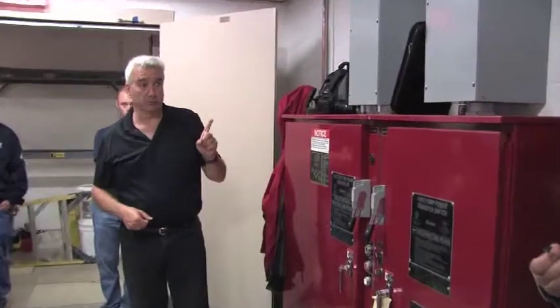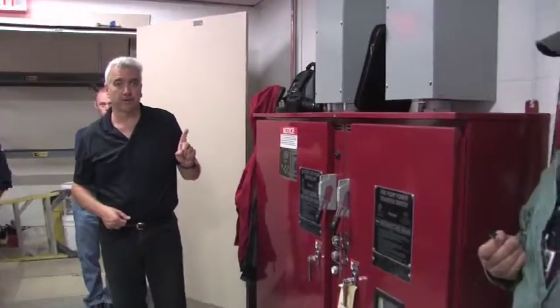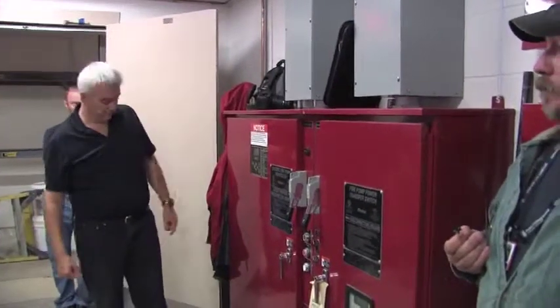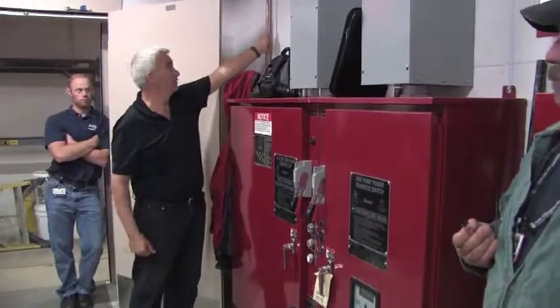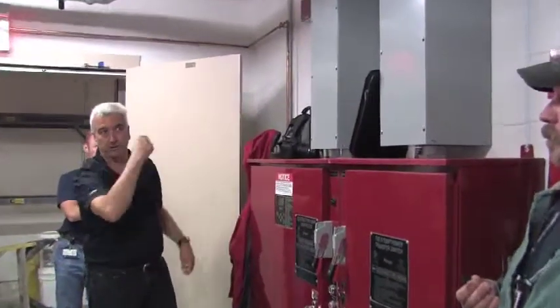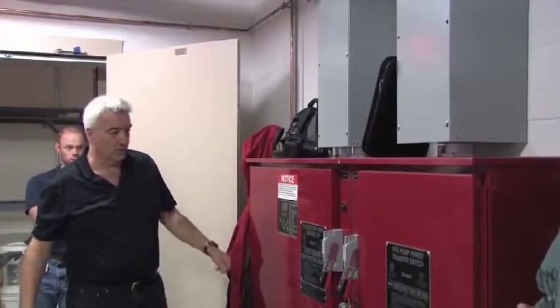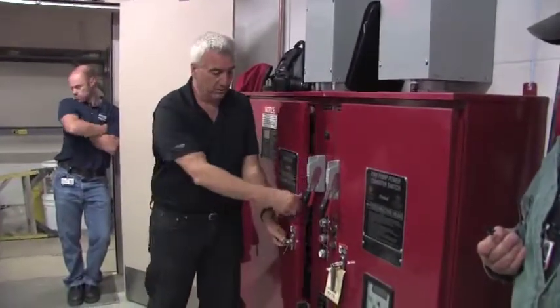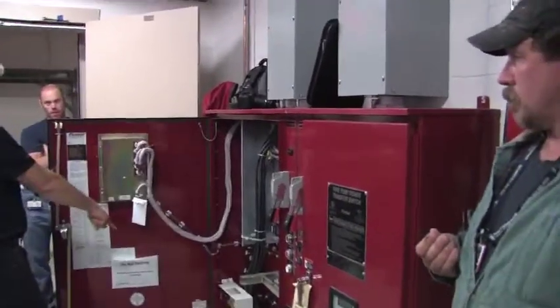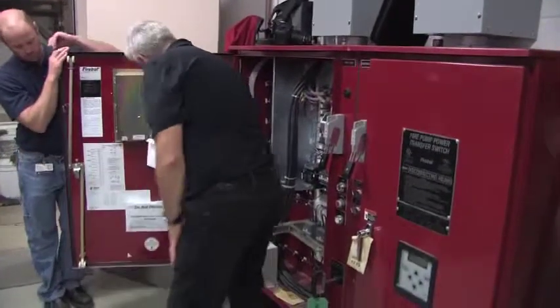I think they're both looking at the same system pressure, right? Same, yes, I believe they're both, yep, tapped into the same sprinkler head. So here's your sensing line for this one. The sensing line is over there for the other one. Correct. Each of these controllers have a transducer. It's located right at the bottom here. So this takes the place of the old Barksdale pressure switches.